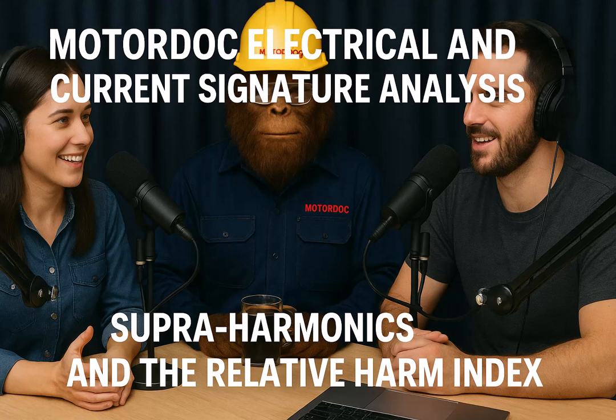And here's a really interesting one. Supraharmonics can sometimes bypass shaft grounding brushes in motors. Bypass the intended ground path. Yeah, because at higher frequencies, the impedance changes. They might find an easier path, a lower impedance path, right through the motor bearing. Through the bearings, what does that do? It causes electrical discharge machining, or fluting. Basically, tiny electrical sparks erode the bearing surface. Not good. Sounds pretty serious.